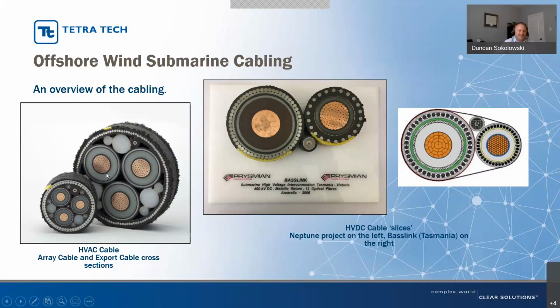We see here on the left, these two slivers are AC cables. They have three power conductors, one for each electrical phase. They also contain one or more, usually a maximum of three, fiber optic packages, which carry data to and from the wind farm. These are contained in a single bundle with normally galvanized steel armoring and covered with a layer of polypropylene yarn. If you look on the right hand side of the screen, we see direct current technology.